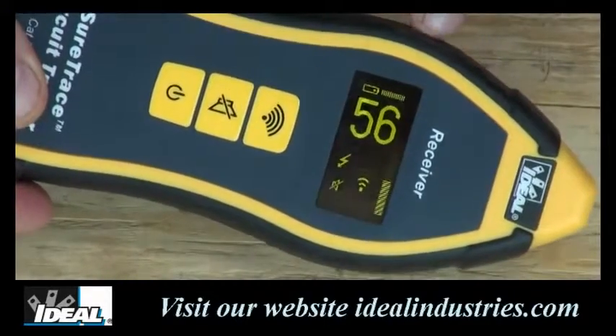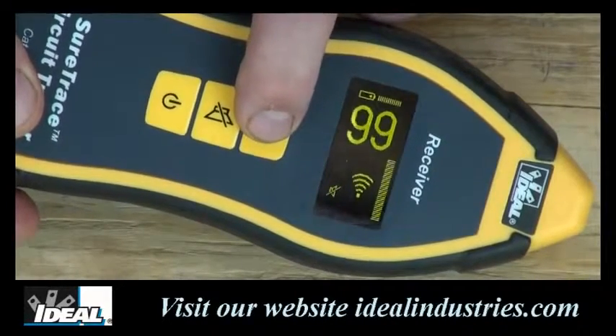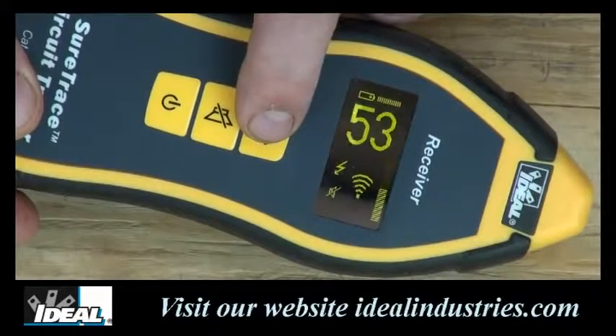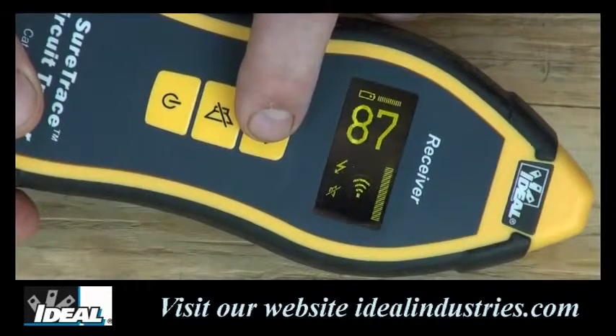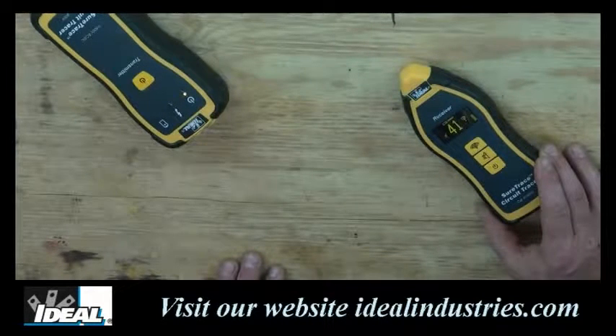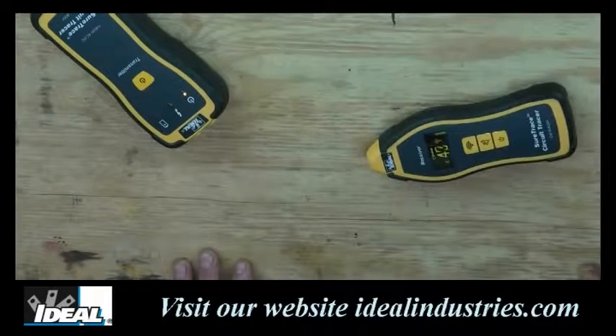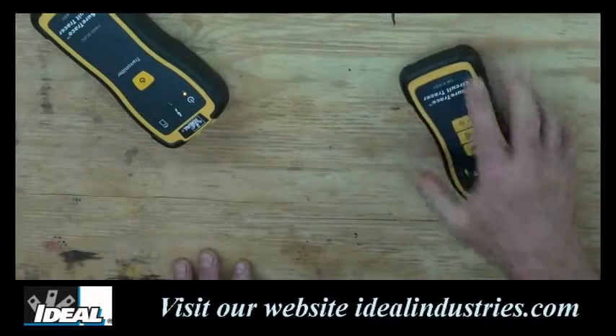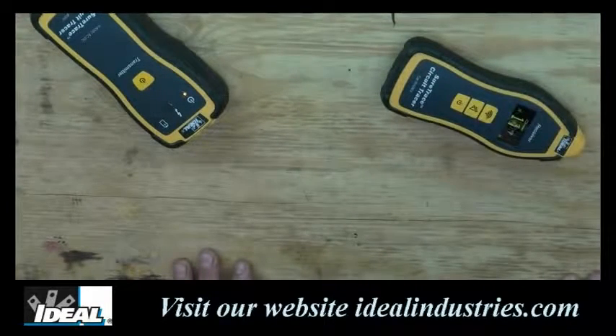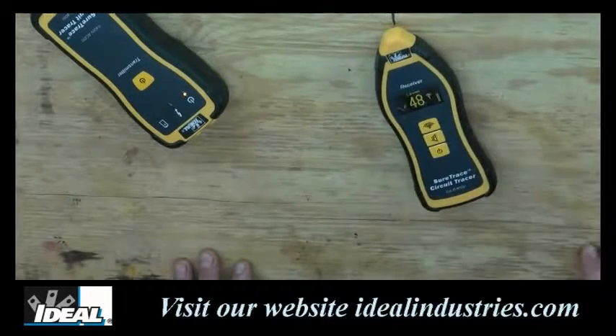The tester has four sensitivity modes with resolution from 0 to 99. Generally start at the highest sensitivity setting first, then use lower settings to verify you're on the correct cable. The intensity of the received signal depends on how the receiver is pointed relative to the source or wire — if pointed away, the value will be very low. As you rotate the receiver about its axis, the signal varies in strength as the antenna points toward and then away from the circuit being traced. I can demonstrate this: as I rotate the receiving unit, the signal intensity does change. Rotate the receiver over the wire until the strongest reading is displayed; if the signal reduces during tracing, the wire may have changed direction, so rotate to find a stronger signal again.